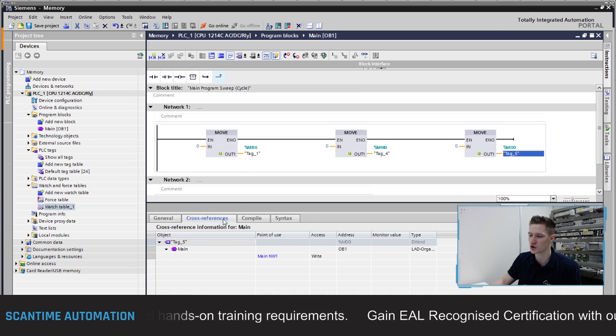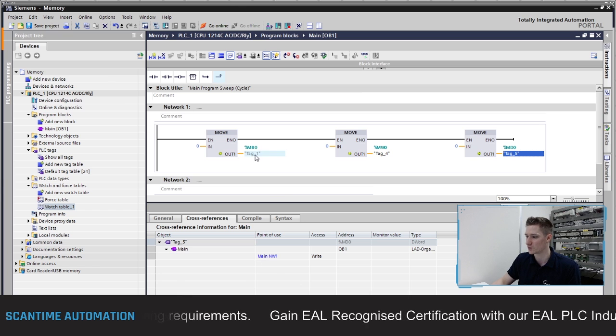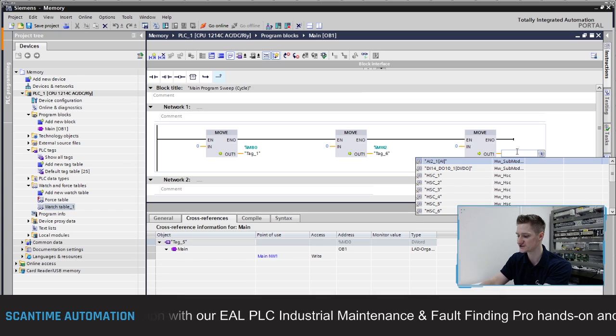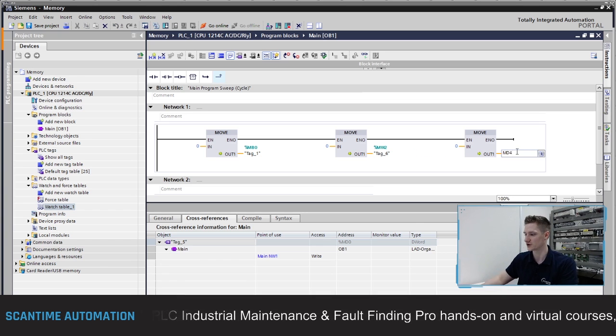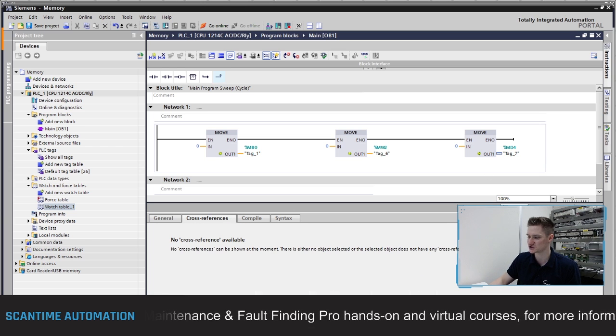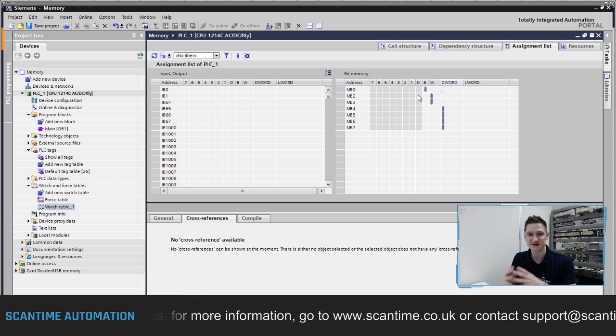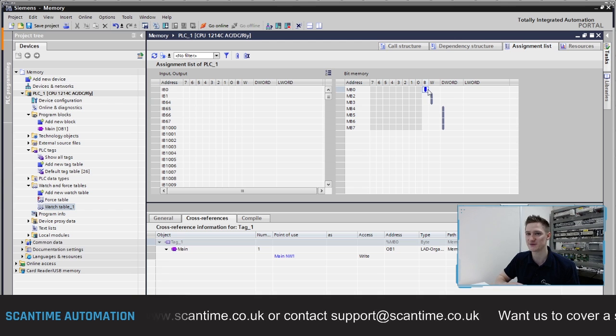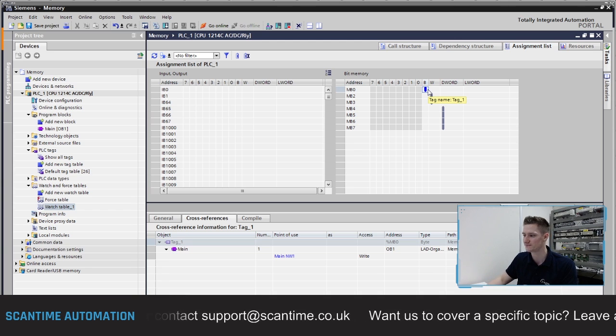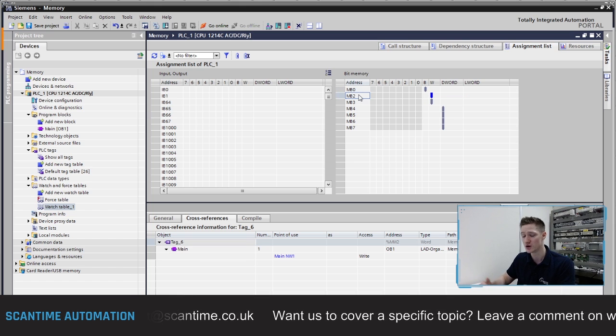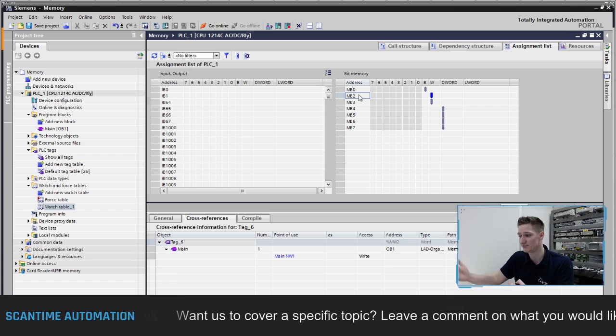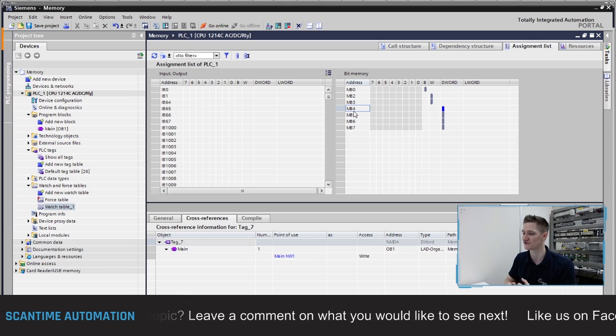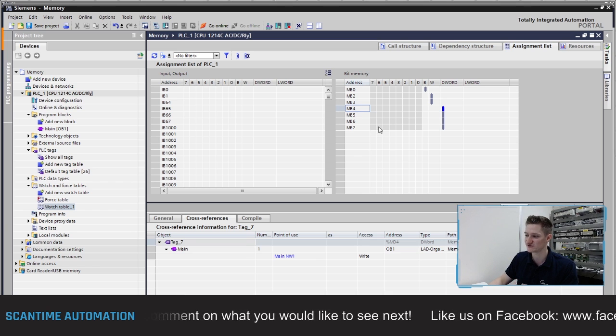To neaten this up, we'd go back to OB1. We've got MB0 here; we could then use MW2, and then for the double word we'd use MD4. Now if we go to our Assignment List, everything is now separated and nothing is overlapping. MB0 consists of bits 0.0 to 0.7. We've jumped to MW2 which uses bytes MB2 and MB3. Then we jump to MD4 - the next available register - which uses MB4, MB5, MB6, and MB7.